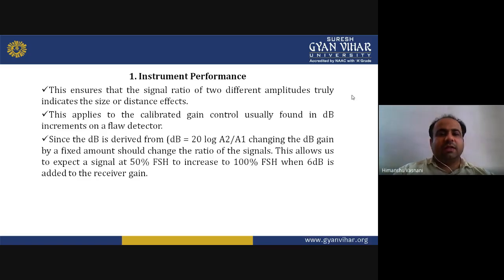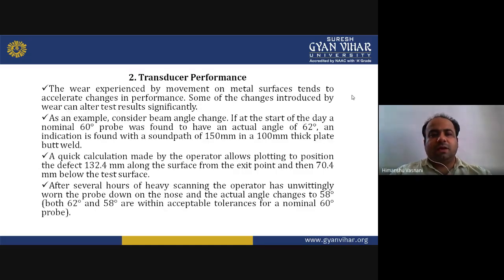This applies to the calibrated gain control, usually found in decibel increments on a flaw detector. Now since the decibel is derived from dB equals 20 log A2 by A1, changing the dB gain by a fixed amount should change the ratio of the signals. Now this allows us to expect a signal at 50% FSH to increase to 100% when 6 dB is added to the receiver gain. Now transducer performance.